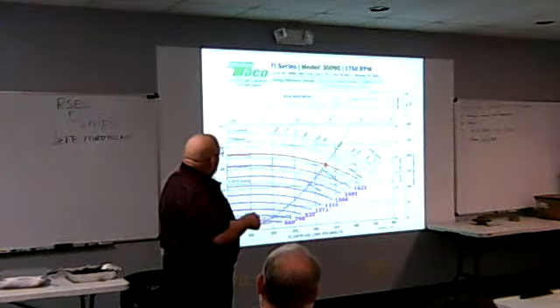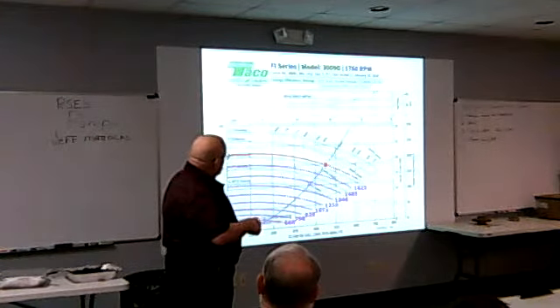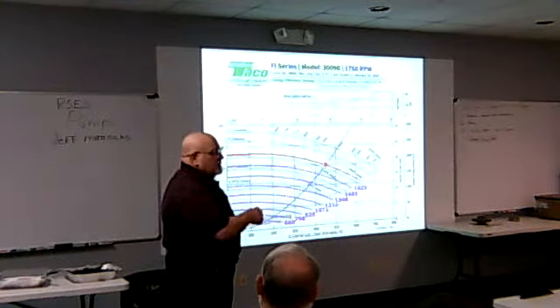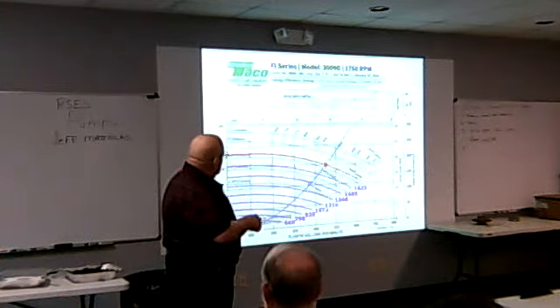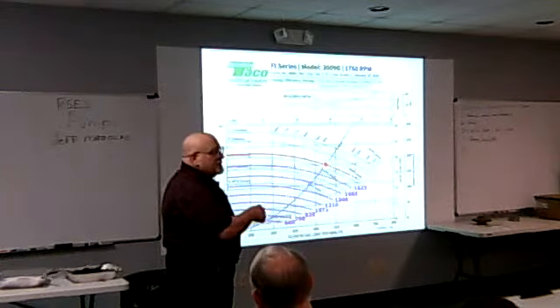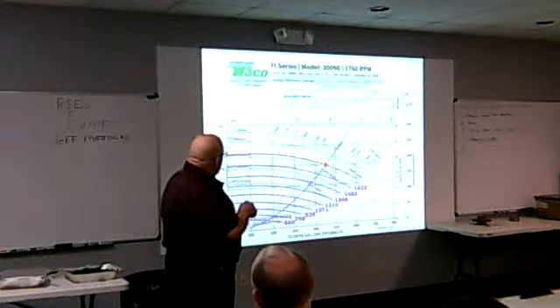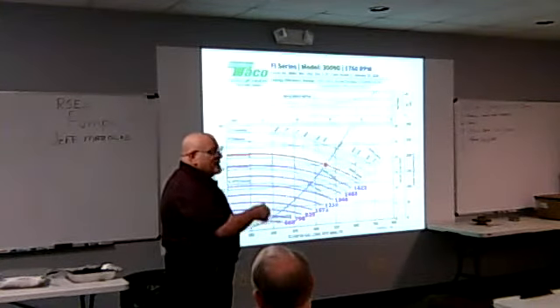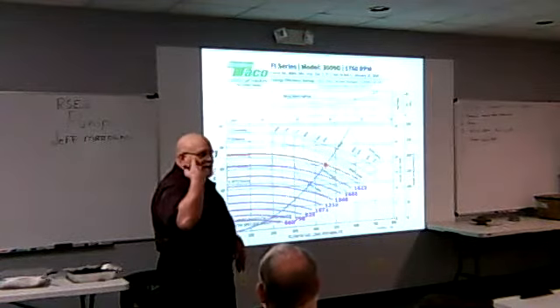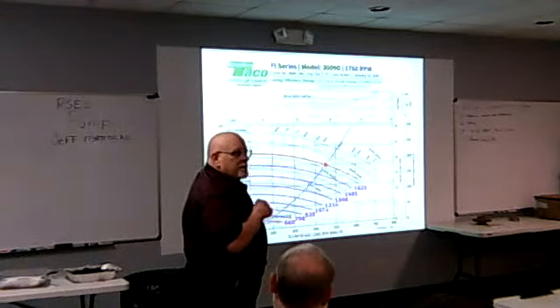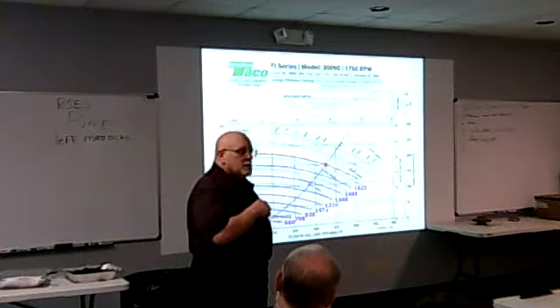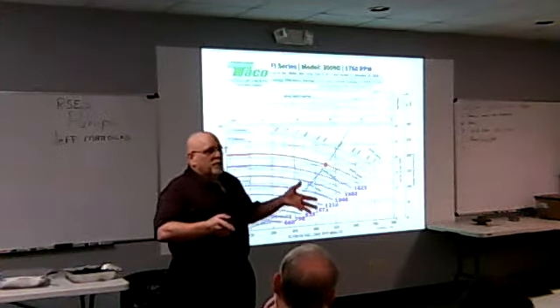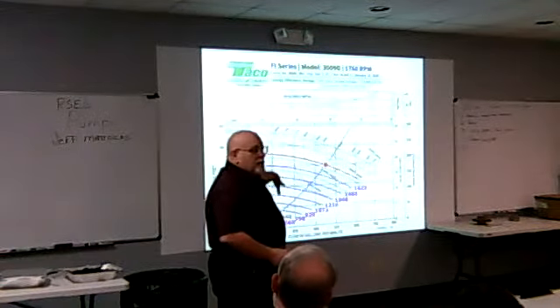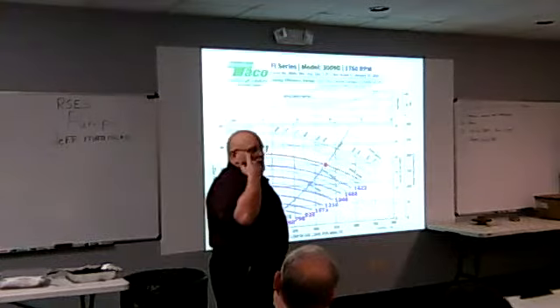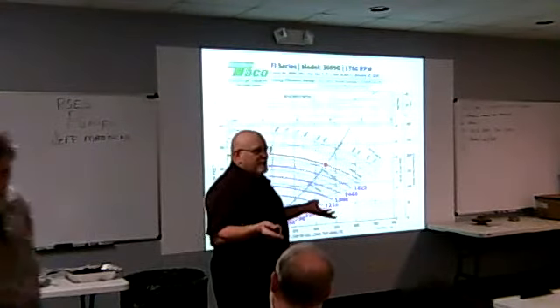And here's our system curve. So as I back my speed down, my flow is going to reduce and walk right up and down this system curve line. At this RPM, I'm going to have this flow. At this RPM, I'm going to have that flow, 1760. Everybody follow that? So it's like trimming the impeller. It's like we did before, except we're just slowing it down and speeding it up. So the speed varies directly. Those purple numbers are the flows? Speed, RPM. If you take a 60 horse motor, go 0 to 60, it's 100% correlated to the speed. So at 30 hertz, which is 50%, I'll be half of 1760, or half of 1160, or half of 3500. Okay.